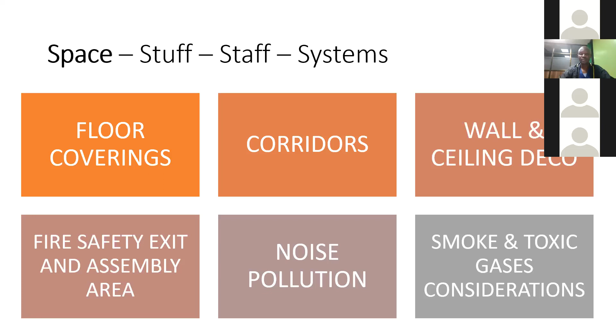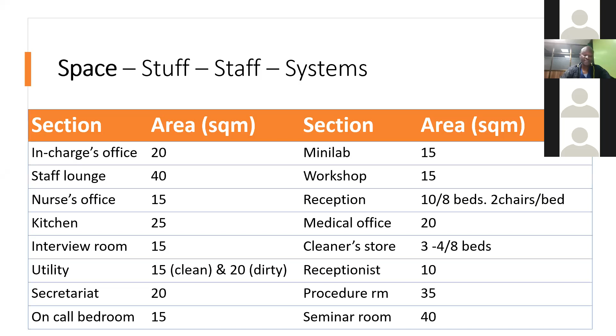So we're still talking about space. Floor layout should include all the sections listed on this slide with their corresponding floor area recommendations. So you can see that's a lot of space for just an ICU. Nursing stations should be situated in a way that nurses can see patients and monitors. Number of isolation rooms with negative pressure should be at least 1 to 6 isolation rooms per 10 ICU beds, depending on where the ICU is. And they should be preceded by an anteroom of about 3 square meters. Storage area of about 10 square meters per ICU bed should be located within 30 meters from the patient space. These are the recommendations for an ICU.